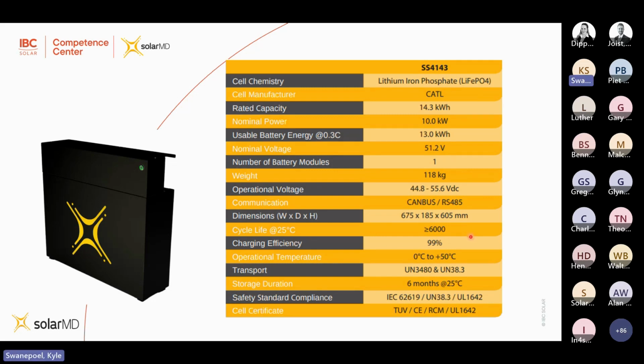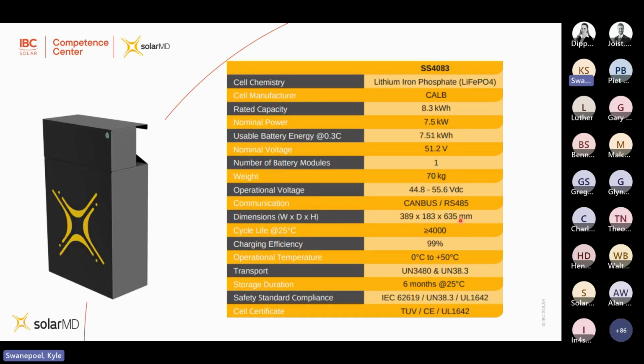And then the next one that we can quickly touch on for you is the new one, which has just come out, which is the 8.3 kilowatt hour. Those of you that are a bit more familiar with the older 3.7 kilowatt hour Solar MD, you'll see the form factor for this battery is very close to what that battery was. So sizing wise, it's really quite compact. This comes in at 8.3 kilowatt hours, and it's rated at 7.5 kilowatts. So this battery has 150 amp fuses, so it perfectly pairs with your 5-6 kilowatt inverters. Weight-wise, just 70 kilograms, so it's quite light. And the cycle life on this battery is 4,000 cycles, and the warranty is also a 10 year energy throughput warranty.